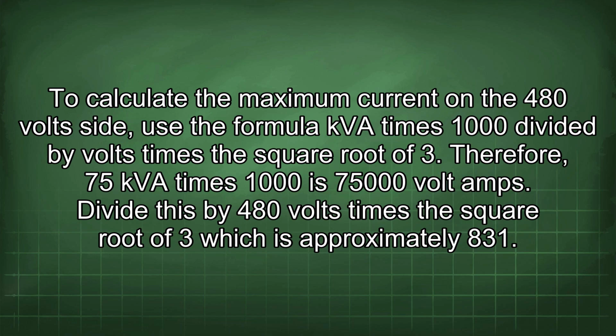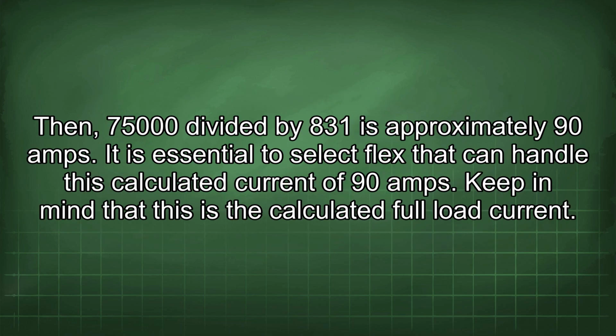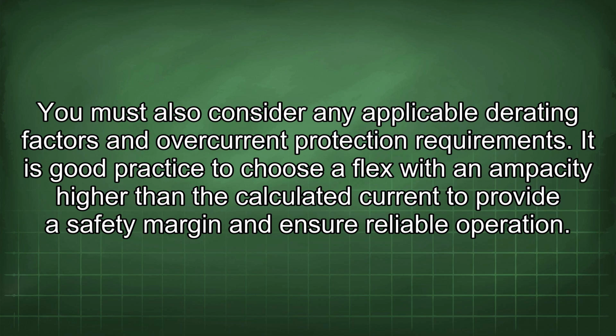Therefore, 75 kVA times 1000 is 75,000 volt amps. Divide this by 480 volts times the square root of 3, which is approximately 831. Then 75,000 divided by 831 is approximately 90 amps. It is essential to select flex that can handle this calculated current of 90 amps. Keep in mind that this is the calculated full load current. You must also consider any applicable derating factors and overcurrent protection requirements. It is good practice to choose a flex with an ampacity higher than the calculated current to provide a safety margin and ensure reliable operation.